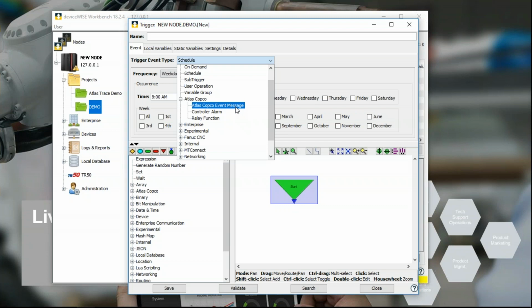You could also get a trace event, if you configure this driver or device to say, in addition to the rundowns, send me the trace information. In the DC tool business, trace means the waveform, the torque curve over time, Newton meters per 50-some milliseconds. So you'll get 800-900 points, and you could plot it and see how every fastening should be alike. If you start seeing trending and deviation, you know something is wrong.